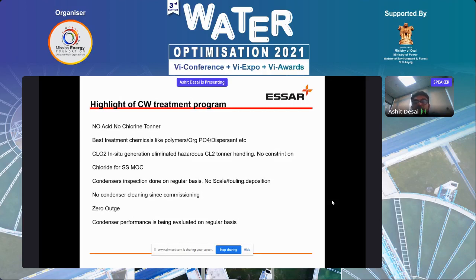Condenser inspection is being done on a regular basis. It's a very challenging job to maintain a cooling water treatment program in-house. Everything we found: no scale, no fouling, no deposit. Corrosion rates are also monitored on a regular basis. All are within the limit, less than 1 or less than 1.2 mils per year. Condenser cleaning has not been done since commissioning. It's a big achievement. Zero outage due to cooling water treatment non-performance. Condenser performance is evaluated on a regular basis, and it is found to be as good as or the same as on the commissioning date.